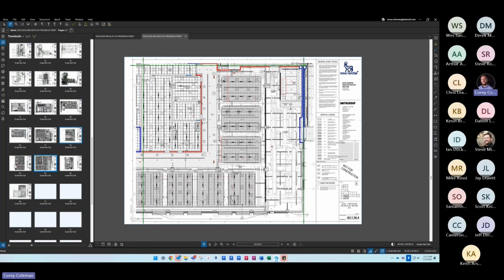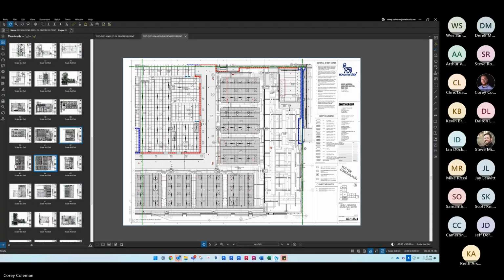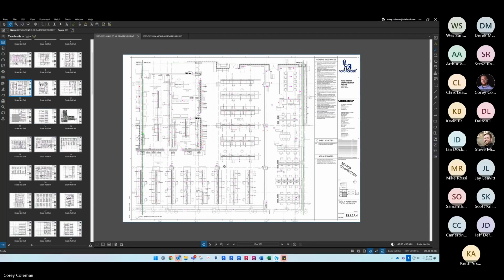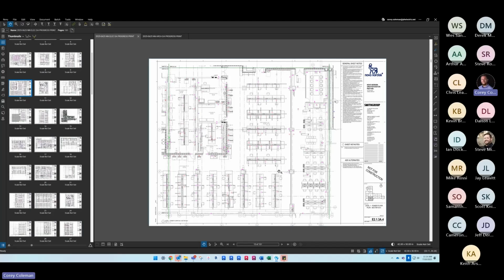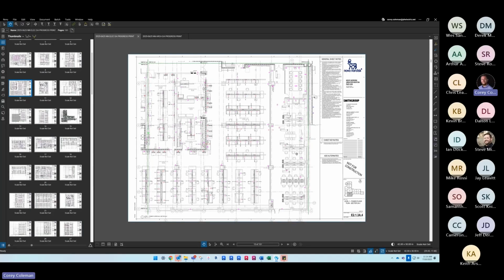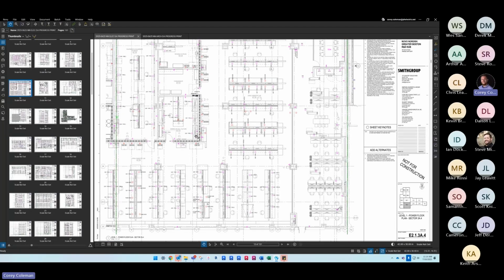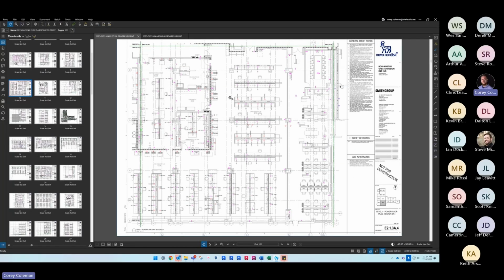So in this area, we have multiple different ceiling types. We have ACT over here. We have gypsum board here. We have floating ACT clouds over here, some soffits, and then just wide open space. In the electrical print, however, when you look at that page, which I think is page 10, none of that information is shown here, right? It's very difficult to understand how you might even be able to pipe over here. Can you do soft cable? Do you have to do hard pipe everywhere?